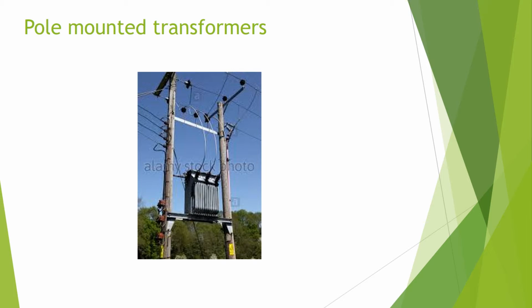The LV cabling is usually wired from the transformer in double insulated conductors to LV fuse carriers mounted on the pole at a safe distance from the exposed HV conductors. From here, customers will be connected via either an LV overhead line or by LV underground cables.